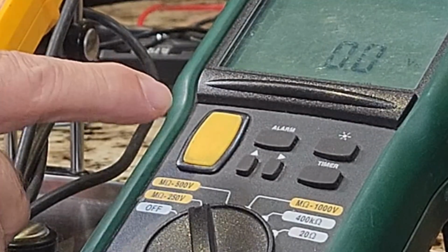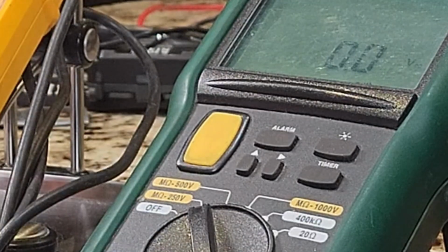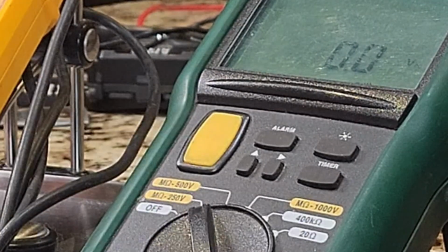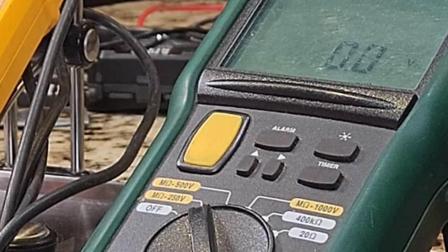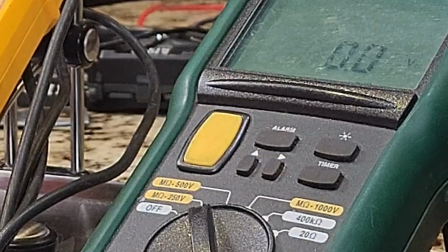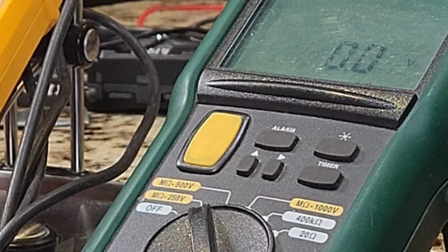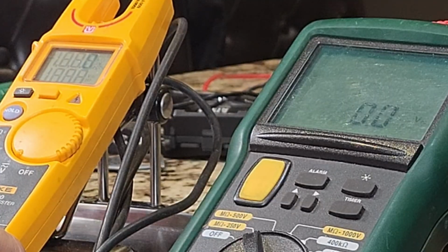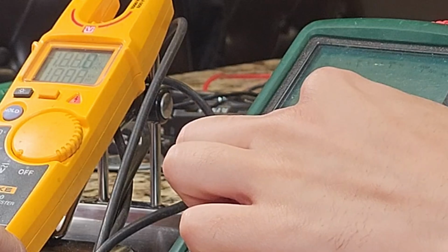Because I'm going to induce 250 volts on this right now, by pushing the test button. But if this was an energized circuit, the unit's smart enough to say, I've sensed voltage, I'm not going to operate. So you have to make sure it's a de-energized circuit. Right? And now we're going to hit the test button. If you want to press that yellow button and hold it.